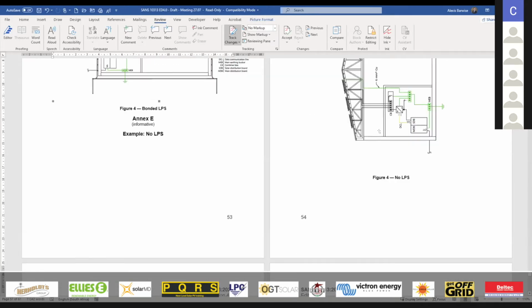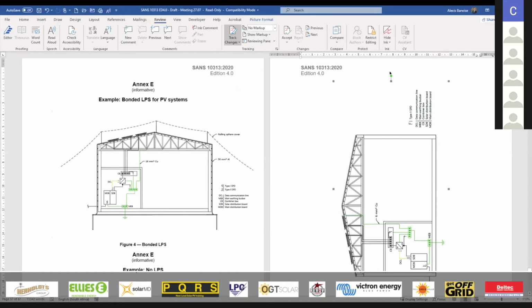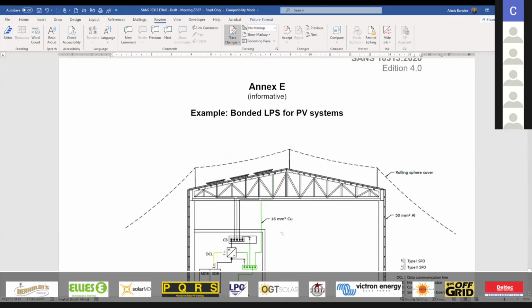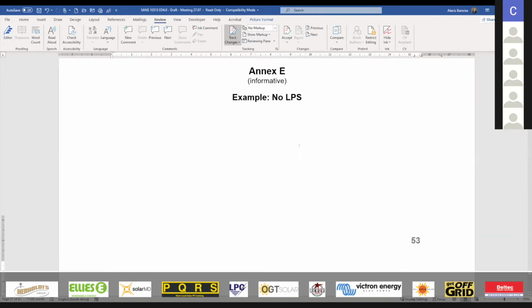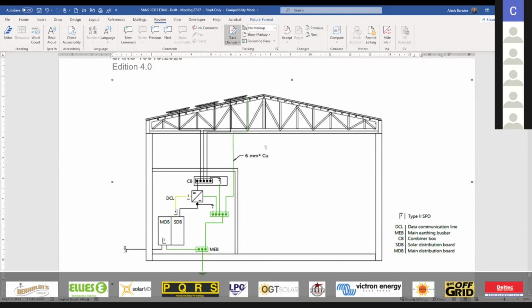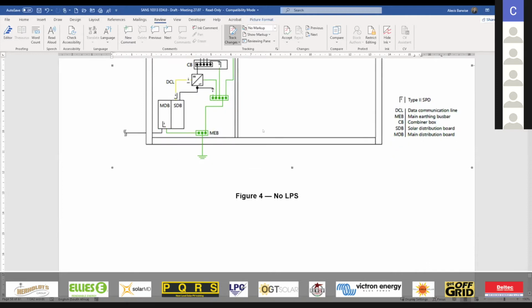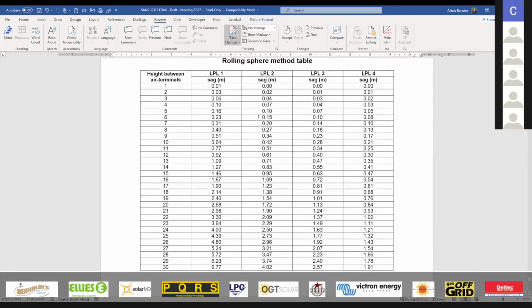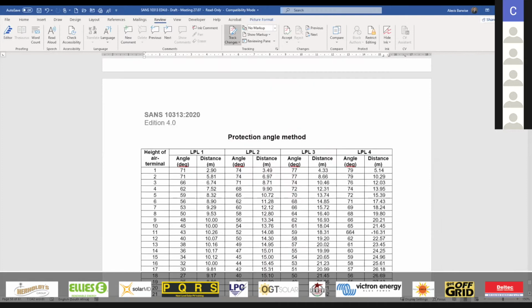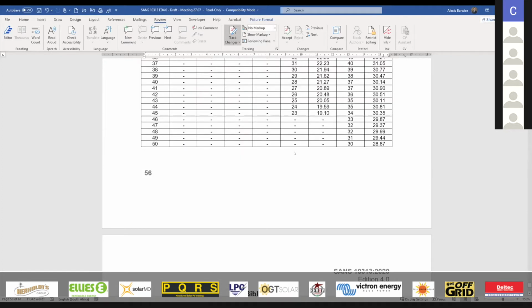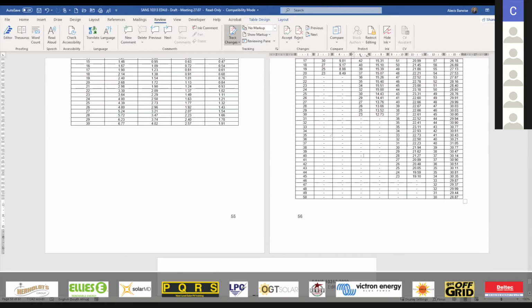And then finally, for a house application, where we don't have any lightning protection system, which is also an option, only surge protection. So there's the copper conductor, 6 mil squared is the minimum, DC side SPD, and that is your typical home application. We've given a nice rolling sphere table to help people, also a nice angle method table to help you place the air terminals.